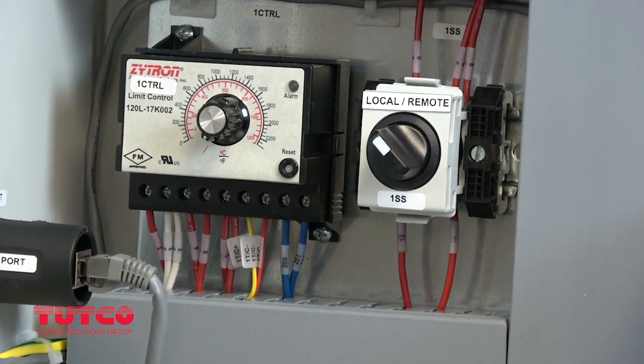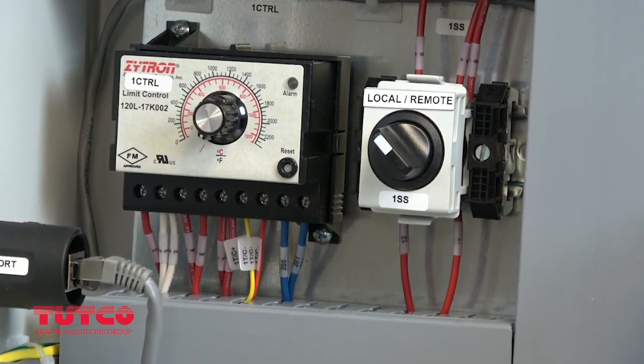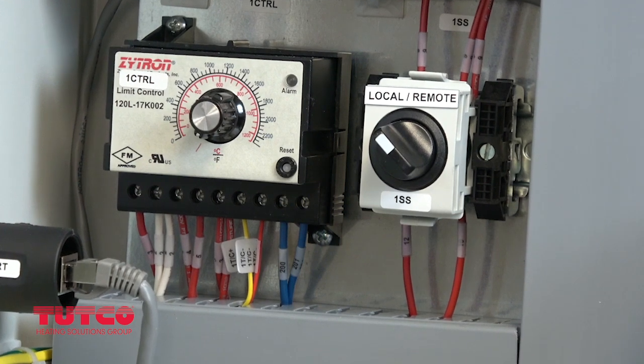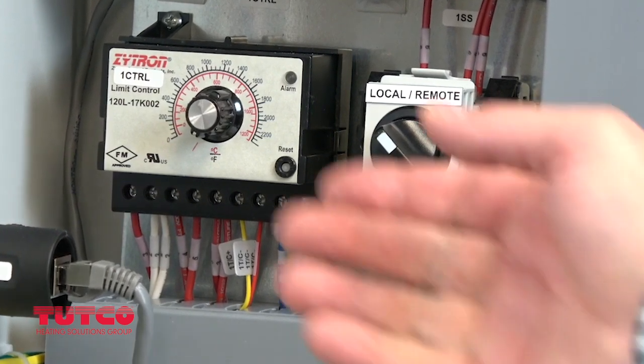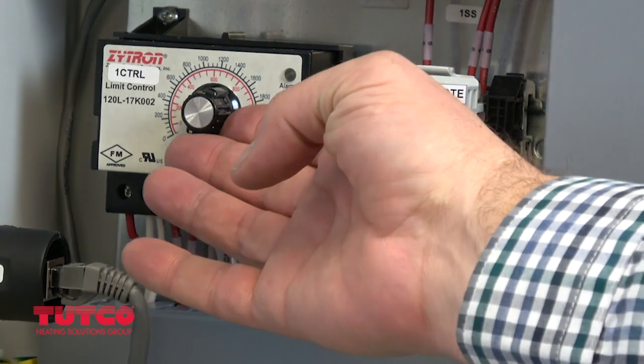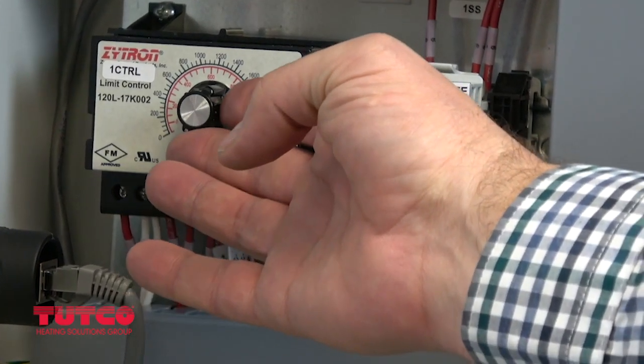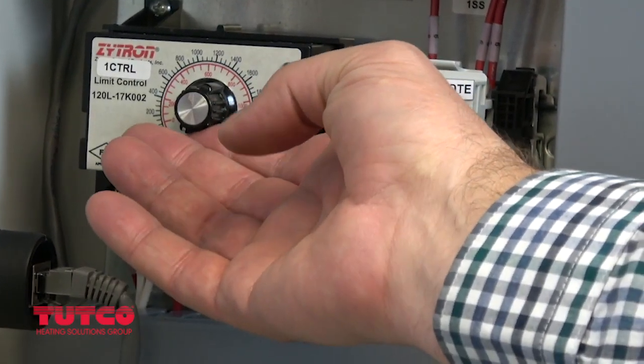The last step before activating the power lines and running the heater is setting the high limit control. Typically, this setting is at 0 as a default. Fahrenheit is in black, Celsius is in red. Be sure to check the heater specifications in the manual for the proper high limit settings.